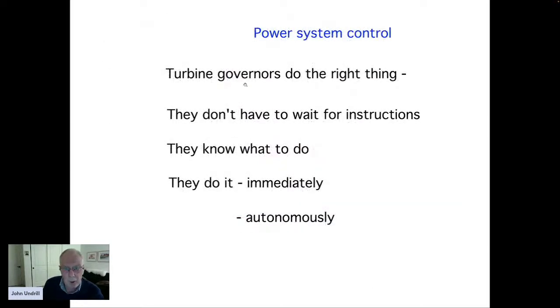So today, as we control the power system, we can trust the governors to do what they need. The primary control of the system, which is the governors operating on the fuel valves of the turbines or the water valves of the hydro plants, does the right thing. It doesn't have to be instructed what to do. It inherently knows what to do. It opens the gates when the speed goes down. It opens the valve as the speed goes down. They do it very quickly, and they do it autonomously. You don't need an elaborate communication and command structure to tell the governors what to do. They're going to respond to a sudden event correctly and effectively.